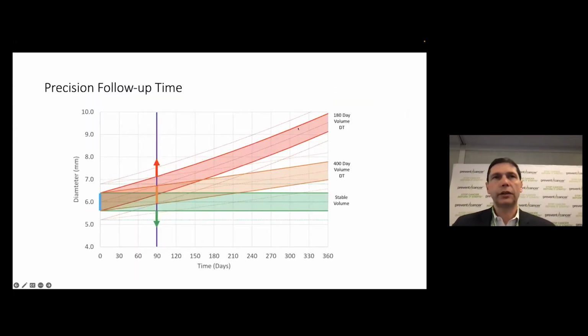One of the things I want to point out to you is that we do encourage everybody to use calibration phantoms. I showed those earlier. What do we get when we get those calibration phantoms scanned and passing at a site? The image quality is passing. We get the precision and any biases of the measurement system. So if somebody was measuring diameter, and let's say it's a 6 millimeter lung nodule, and it has a 1 standard deviation of precision of 0.5 millimeter, which is pretty good, that's 0.5 pixel for a large patient.